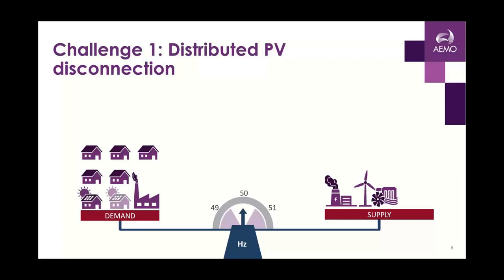The way that PV is impacting our work is that we're seeing so much PV come on that we now have to think about it as a supply side, because it's actually a generator. It's something we have to think about on this right hand side, even though it comes from the demand side. As we get more and more rooftop PV being installed, we now have to consider a larger amount of solar on the supply side. And we also have to curtail some of the other generation operating at that time.